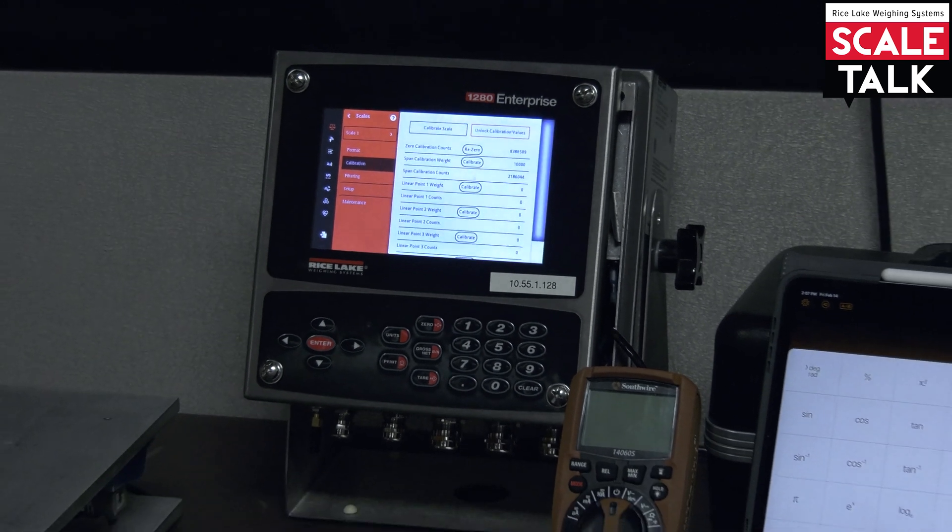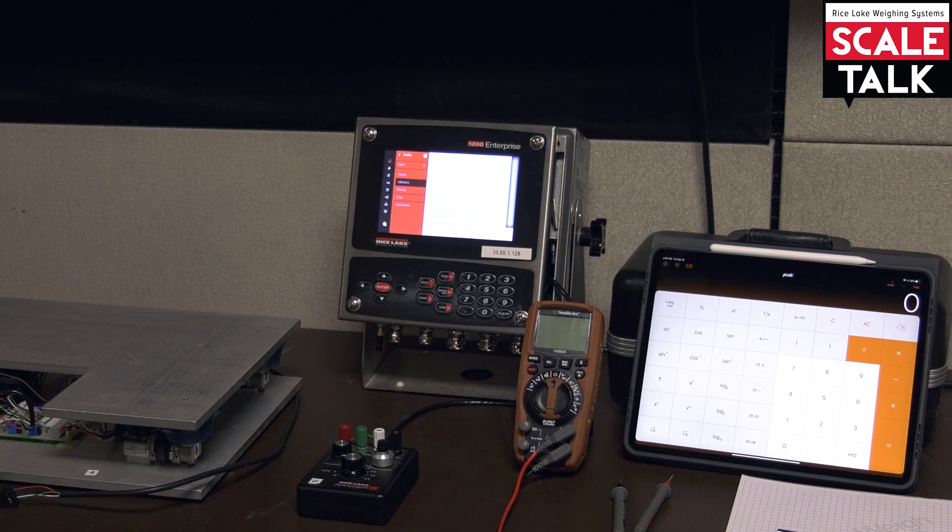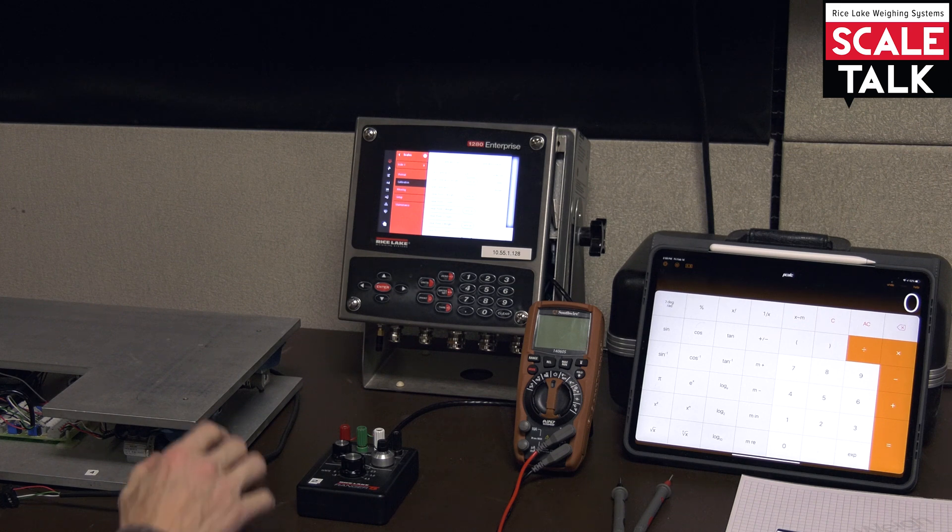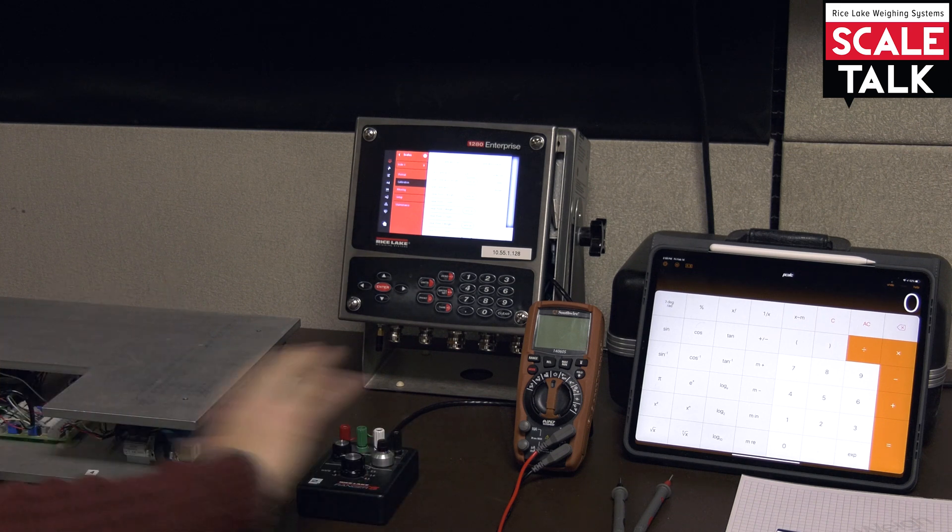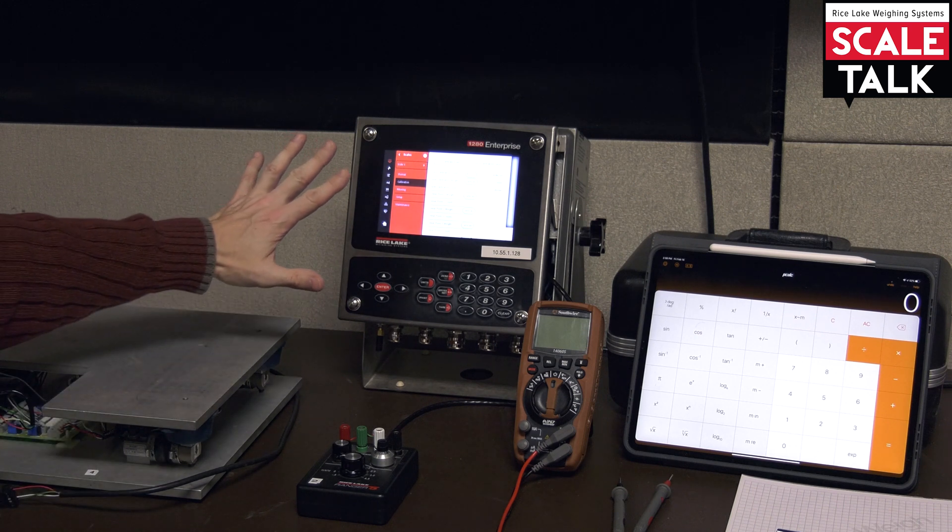Now in order to calibrate with a simulator there's some additional information that we need to know. While this might be the least accurate, it's not the same as simply going from zero to span on the simulator. It's probably one of the more difficult methods of calibration even though it's the least accurate because it involves getting some data and doing some math.